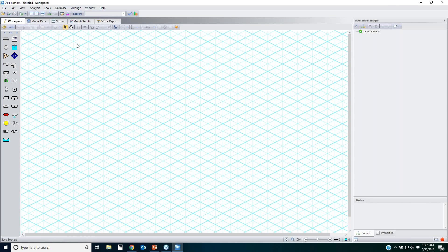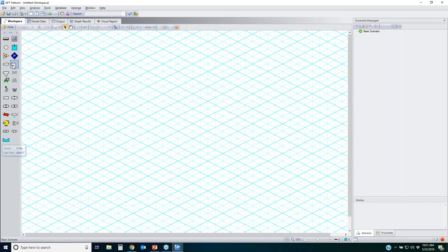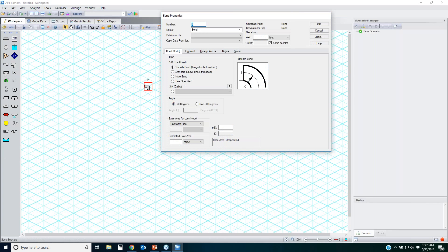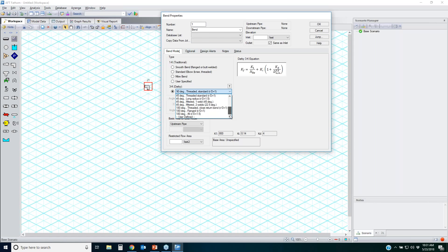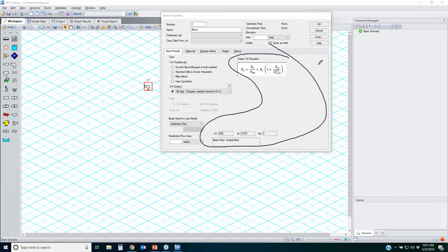Once you choose Include 3K from Darby, the window changes — when you go into an elbow, you'll now have a new 3K option with different fittings you can apply it to, along with the 3K values and the exact equation showing how the factors are applied. That's how you turn on the 3K method. Remember, it can only be used for certain types of losses.